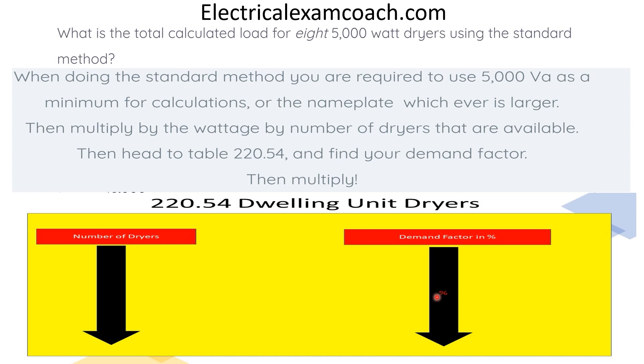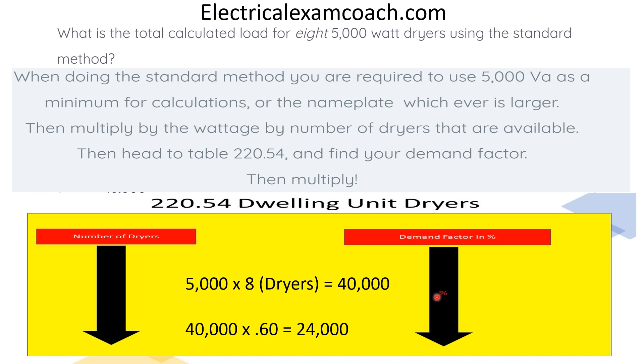Make sure that you use a straight edge on this table so you don't get crossed — use a piece of paper or a pencil. We take our 5,000 per dryer and multiply it by our number of dryers. Then we take that total demand and multiply it by the demand factor. That gives us a new reduced load of 24,000 watts.